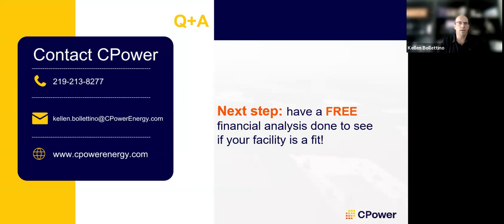Even if the generator isn't approved for participation for whatever reason, if it has the option for a retrofit or a simple update, we can provide high-level estimates of the cost and bring that back to the provider of the generator. Usually it can be less than a year ROI, depending on the program participation for that retrofit. Once that's done, the generator's compliant in the market for, I'd say, the next 20 years or so, until it needs to be replaced. These stipulations that FERC put through about 5 or 6 years ago aren't going to change anytime soon, so they're the standard for the long haul.